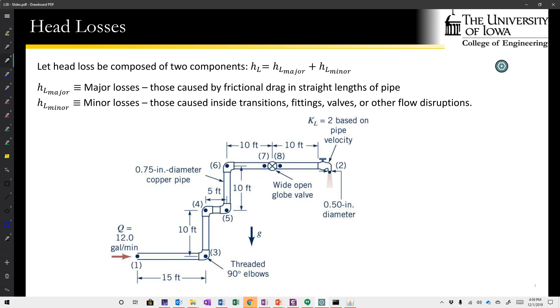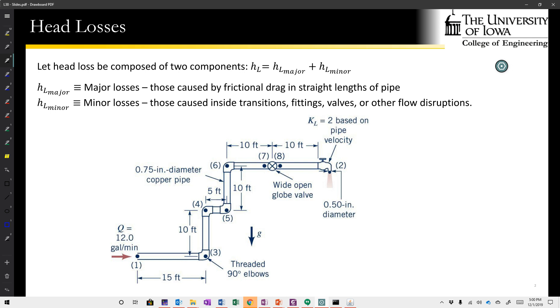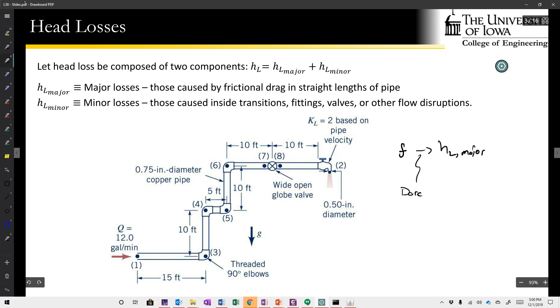We introduced the idea of head loss through the context of the energy equation when reformed into what we call the head equation. The total head loss H_L is composed of two parts: the major and the minor head loss. The major head loss is composed of the frictional losses in straight lengths of pipe, calculated using the Moody diagram, which gives us a friction factor f that we turn into the major head loss through the Darcy-Weisbach equation.